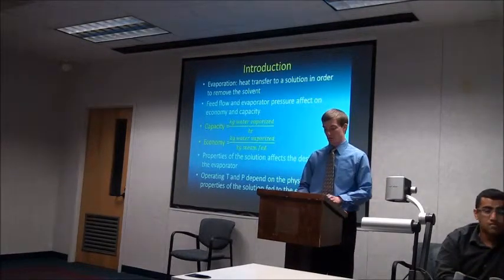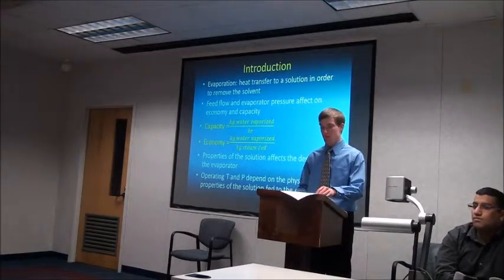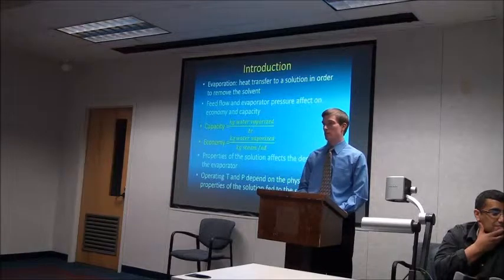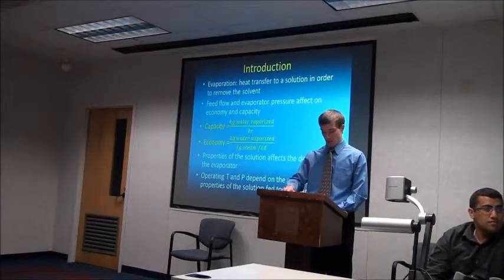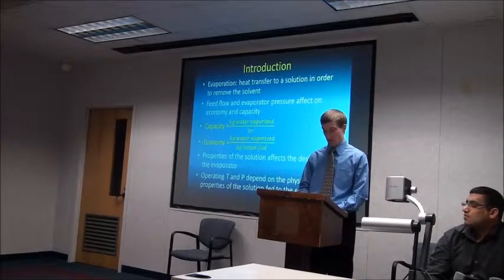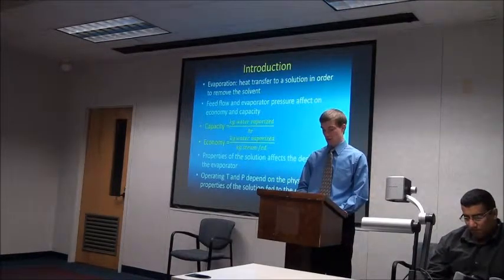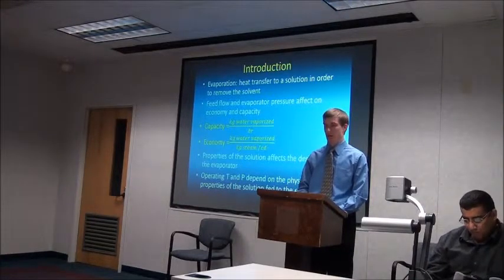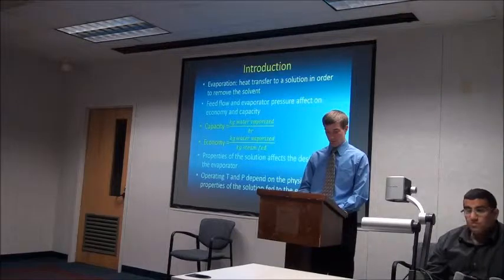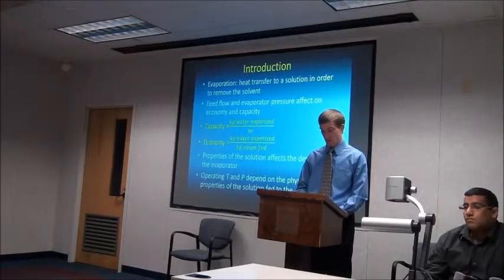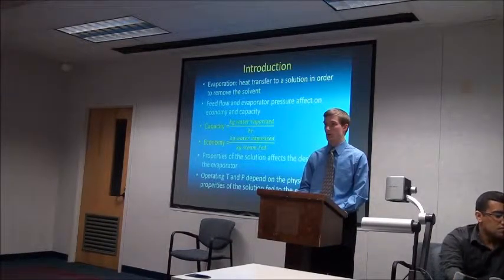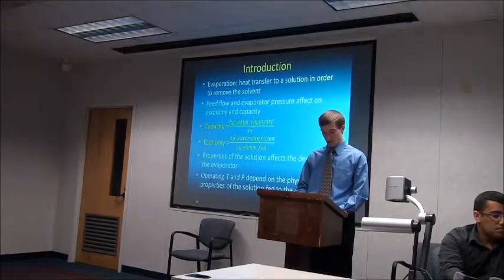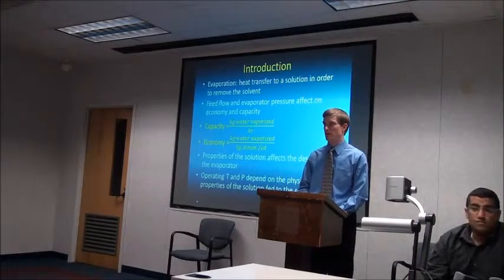Evaporation is a process in which a solution is heated in order to remove a solvent. The feed flow and the evaporator pressure have an effect on the economy and the capacity. The economy is kilograms of water vaporized versus kilograms of steam fed, and the capacity is kilograms of water vaporized per hour. The properties of the solution affect the design of the evaporator itself.